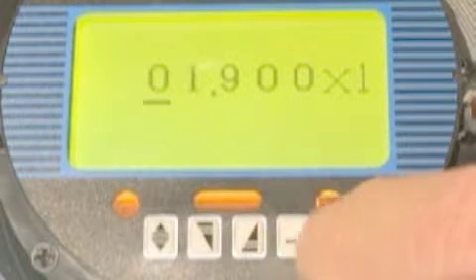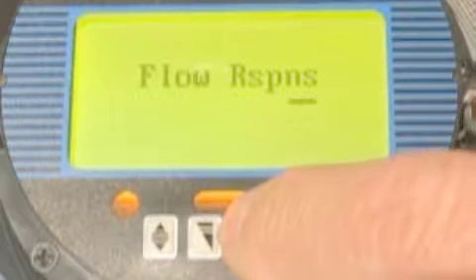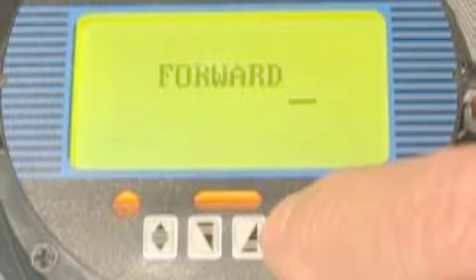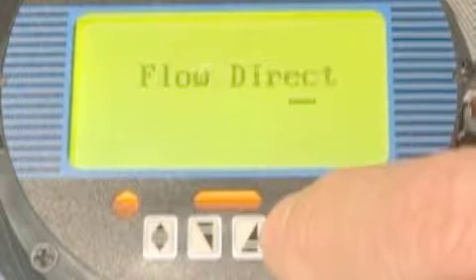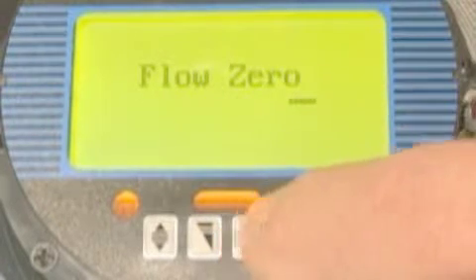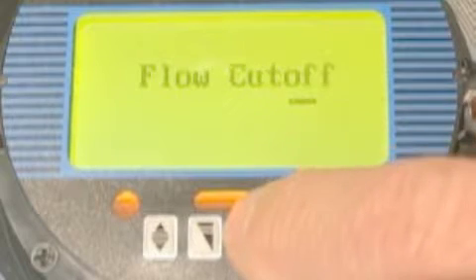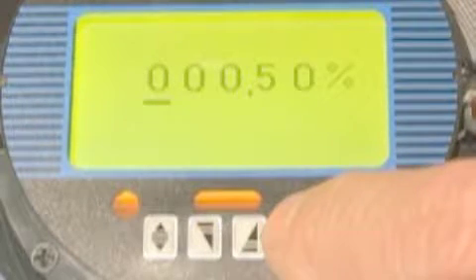The flow range, we can set the flow range based on the units. And you can set the flow response, four seconds for this one. Let's slow it down. Flow direction, forward or reverse. You may want to change that at times if you're pumping flow zero. This drives the DACs and everything. The flow cutoff, what percentage? It'll call it zero.